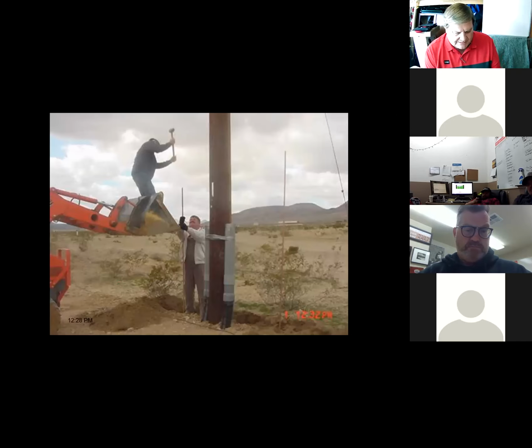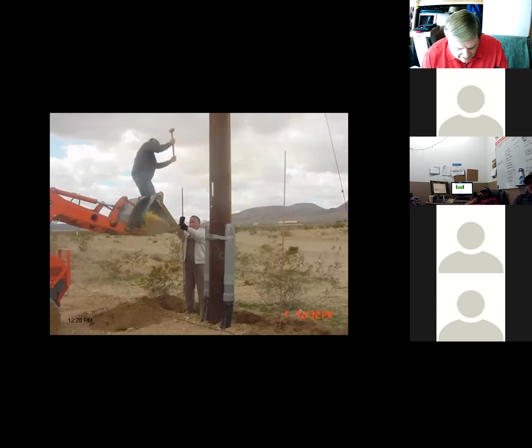It's a critical piece. Now, I don't have an idea why this guy is smiling, first of all. Two, the guy on the makeshift ladder is not an appropriate OSHA-style design setup. This isn't safe. One missed swing of that hammer and that guy's gone. Oh, by the way, in case you're wondering, National Electric Code requirements state that a ground rod, if it's 10 foot like it looks here in the picture, needs to be 10 feet away from the pole we're protecting. This ground rod here is like 4 feet away, and that one is maybe 2 feet away, a body length. These aren't being installed in the proper location, nor by the proper people.